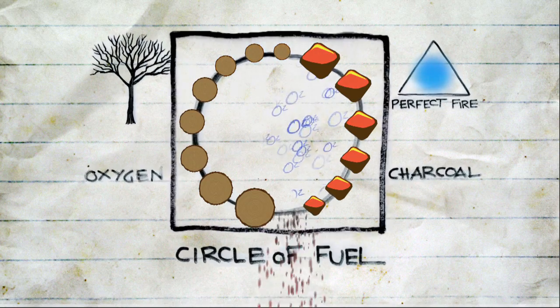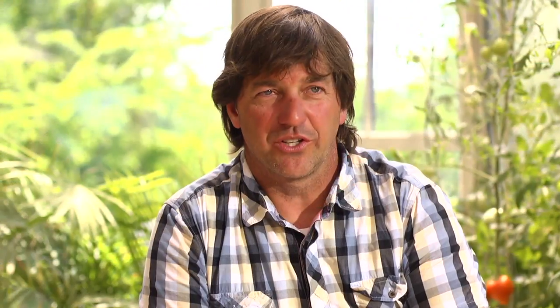We need to control that environment. When we control that environment, we measure exhaust temperature and match it with our incoming air. We can hold that exhaust temperature plus or minus five degrees. Set it at the right temperature, get our internal temperatures where we need it, and the gasification takes place — so we don't go out of gasification, but we don't go higher than gasification either.